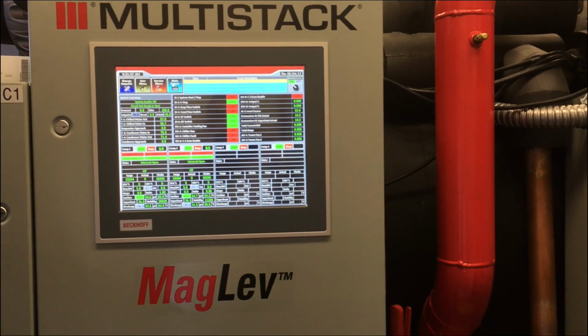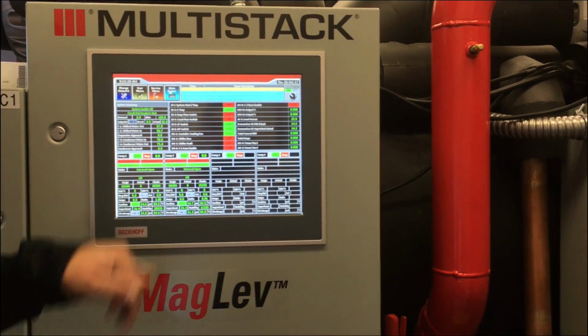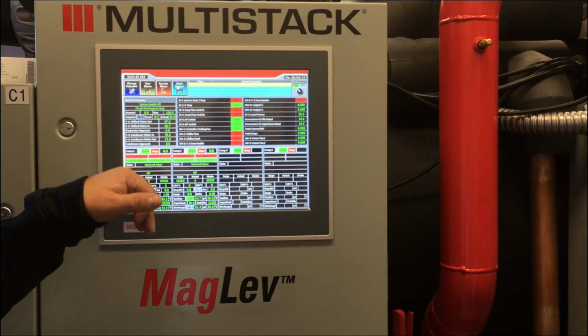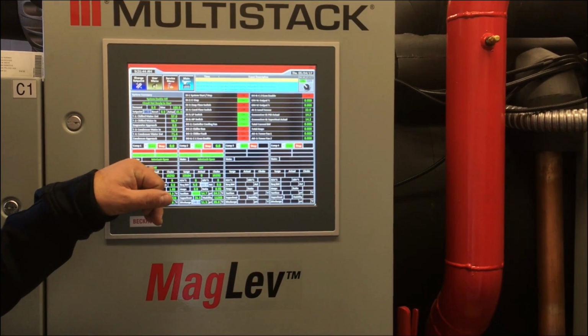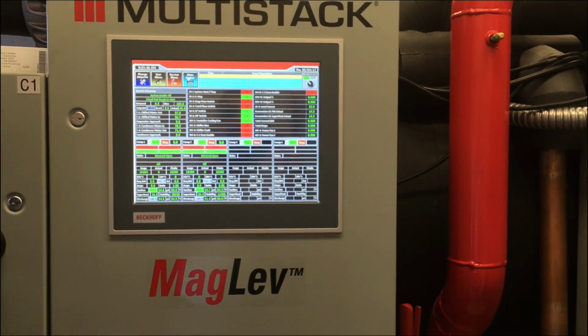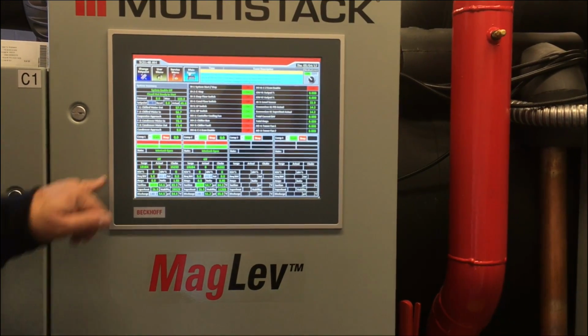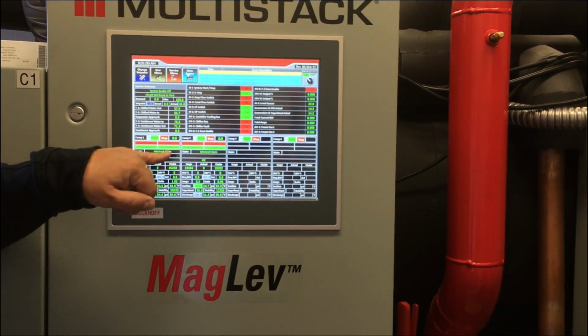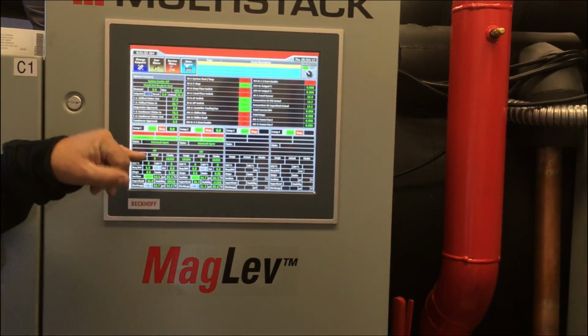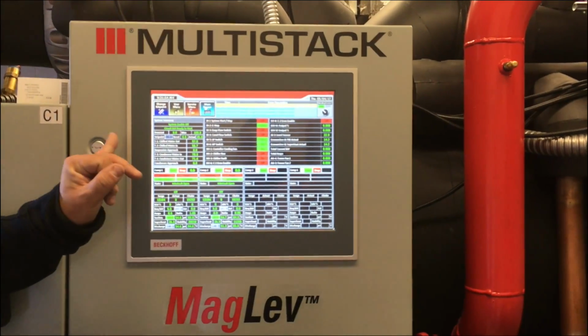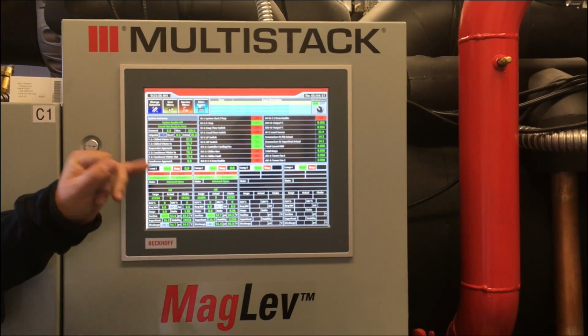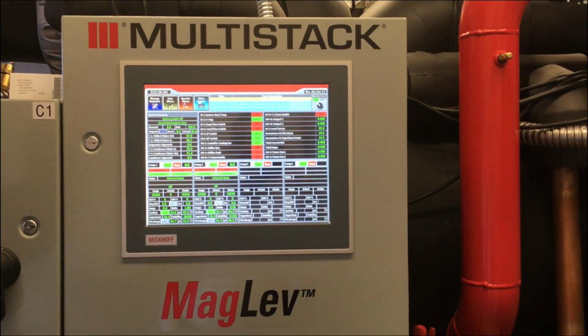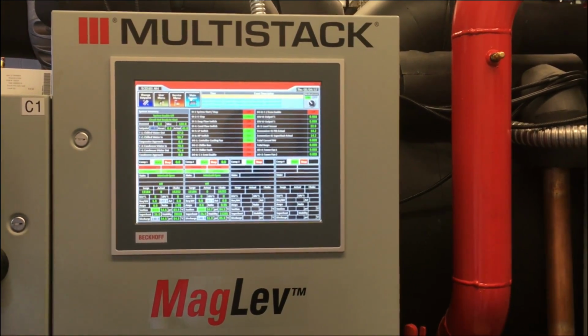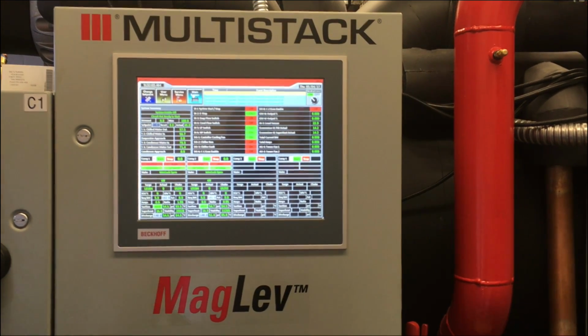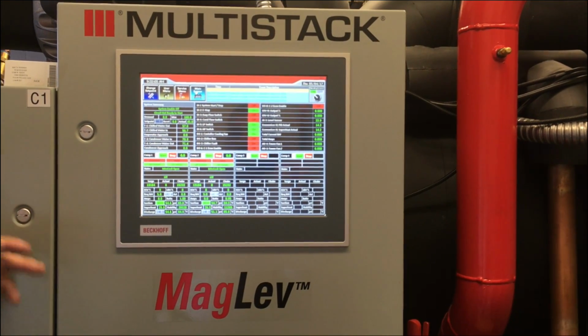So right now, we're disabled because we're not calling. So the interlock to the compressor is open. So the compressor's off. Everything's in plain English. If there's a fault with the compressor, this may say bearing motor fault across the top. Bearing motor fault is 14 items, and 12 of those are minor. It could be anything, like when you lose power, you create a bearing motor fault because the power to that magnet, even if it's not being energized, is always there.